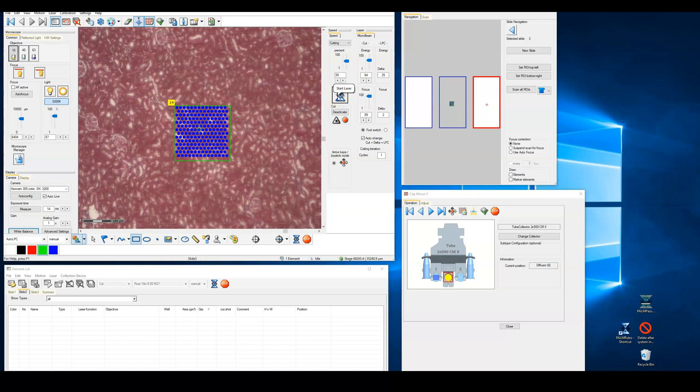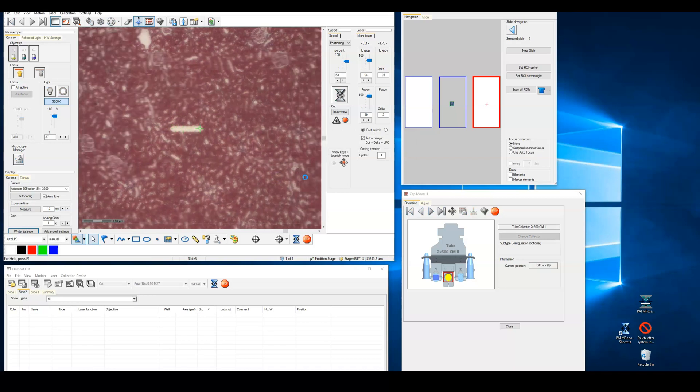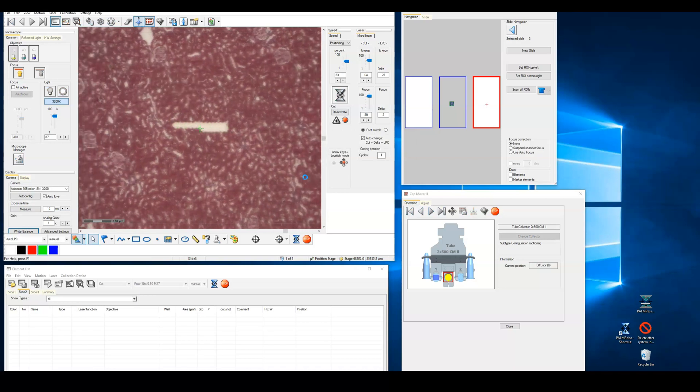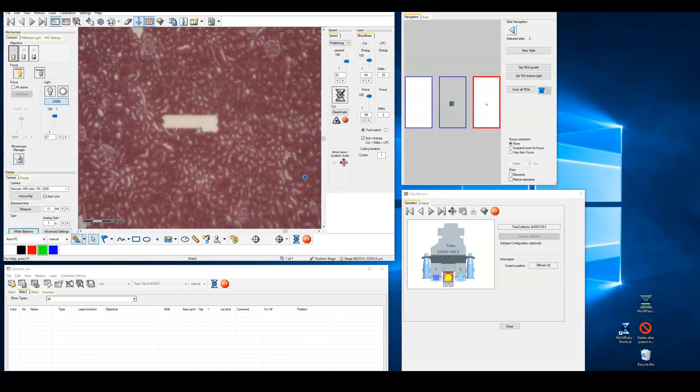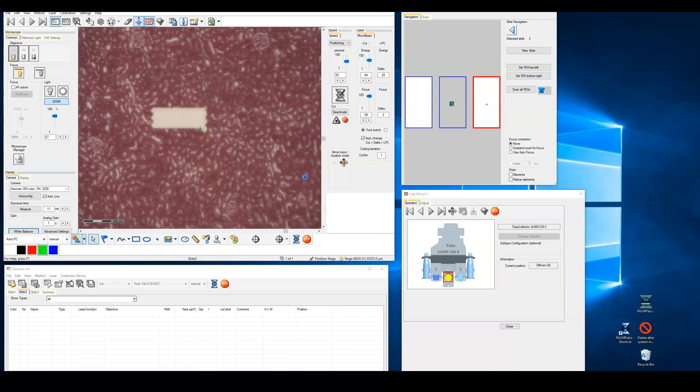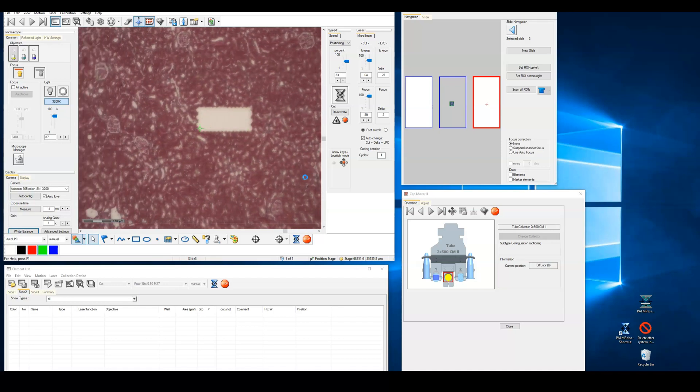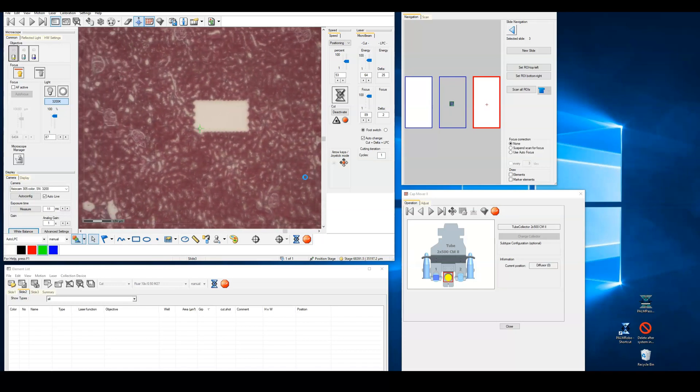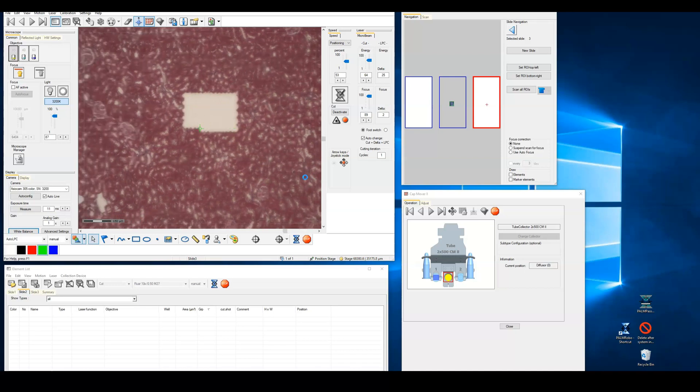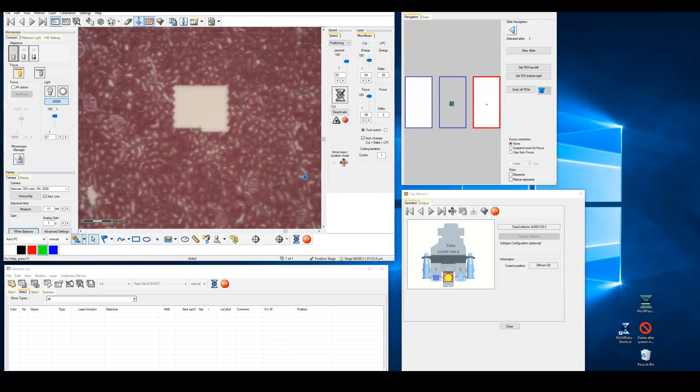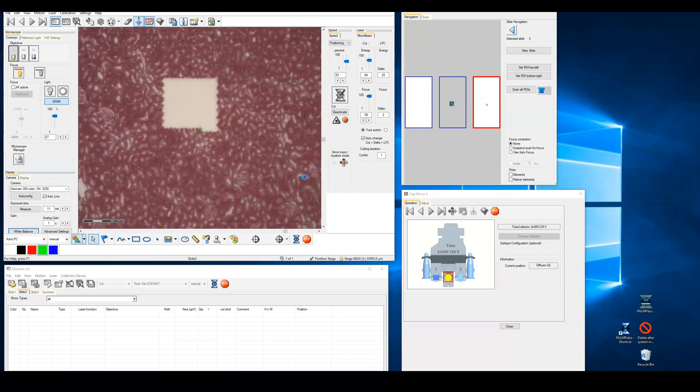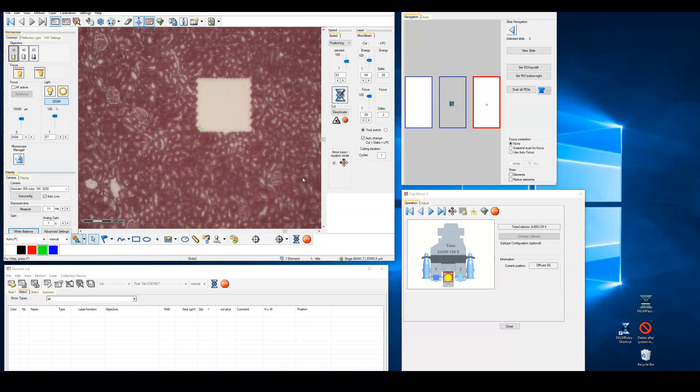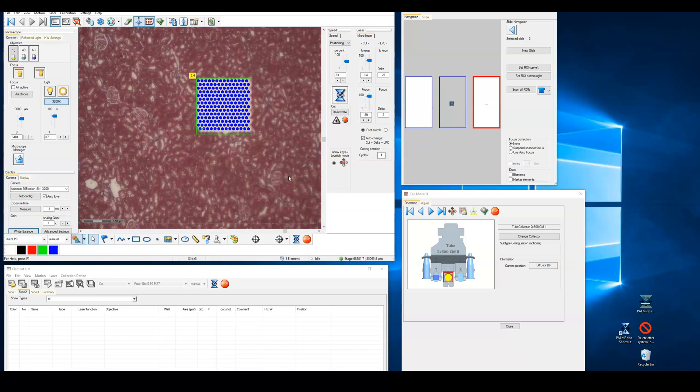Alternatively, we can use a closed cut and auto-LPC, which will define the boundary of the tissue first with an ablation line before isolating with catapult pulses. Here we can see an example of what the auto-LPC process looks like. Using the auto-LPC, the fragments of sample will be collected in the capture tube, but will not be visible in the manner that a single large fragment is, as we demonstrated at the beginning of this tutorial. The auto-LPC may be done in a line if the membrane regions are to be isolated from tissue, for example.